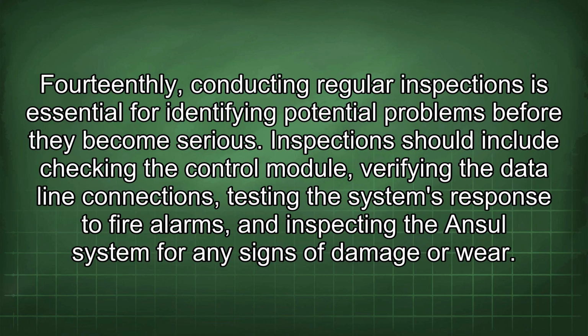14thly, conducting regular inspections is essential for identifying potential problems before they become serious. Inspections should include checking the control module, verifying the data line connections, testing the system's response to fire alarms, and inspecting the Ansul system for any signs of damage or wear.